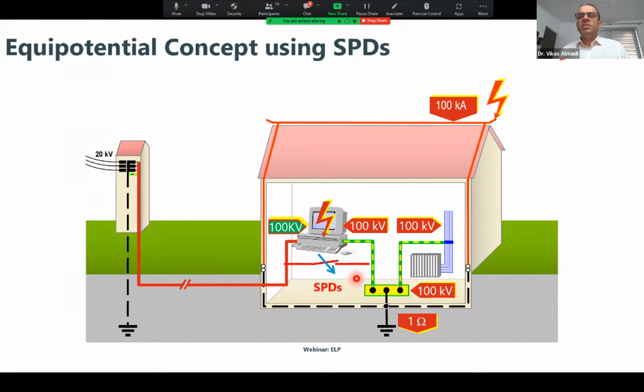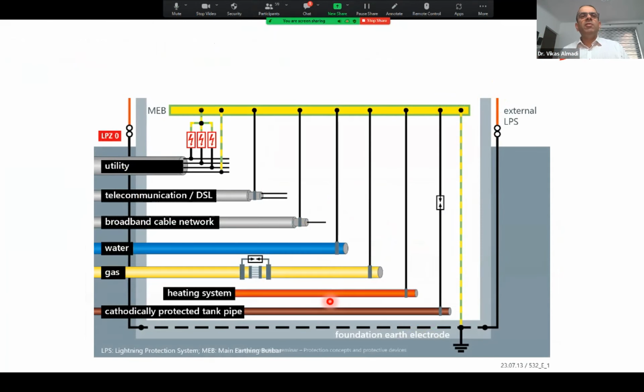So SPD is creating an equipotential bonding, and without the SPD, even lightning protection is not complete because it will still kill the equipment. So SPD becomes a part of the lightning protection also. This is important to understand. Without SPD, the comprehensive lightning protection is not complete. That means everything in our building or our infrastructure should be at the same potential when there is a lightning strike. The live conductors, which we cannot connect directly to each other or to earth, we have to connect them via the SPDs, which are normally in the off condition. That means normally they are creating the isolation, but when there is a surge or lightning, they are creating equipotential bonding. So everything has the same potential.